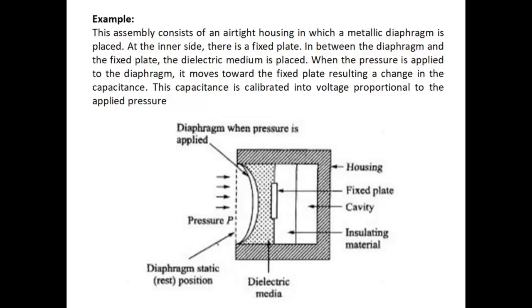Instead of a capacitive structure, another example is to place a piezoelectric crystal just below the diaphragm. When pressure is applied, the diaphragm bends, and that bending is introduced into the piezoelectric crystal, which then gives a corresponding voltage signal.